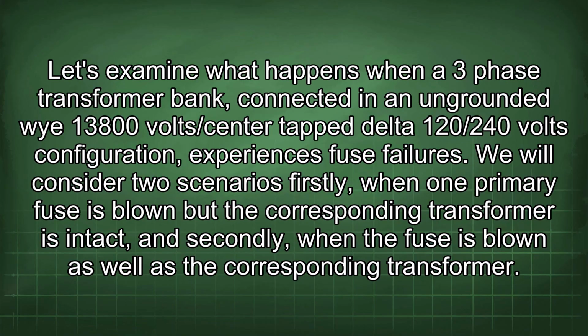Let's examine what happens when a three-phase transformer bank connected in an ungrounded Wye 13,800 volts/center tap delta 120/240 volts configuration experiences fuse failures. We will consider two scenarios. Firstly, when one primary fuse is blown but the corresponding transformer is intact, and secondly, when the fuse is blown as well as the corresponding transformer.